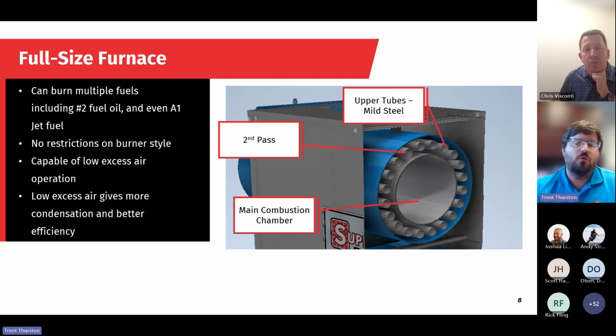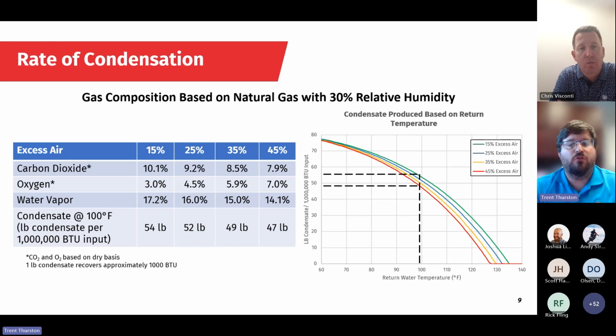Excess air causes a couple issues. One is that you're heating up unnecessary air, and so you're wasting energy by doing that. With condensing boilers, there's another aspect, is that you get better condensation with lower excess air levels. So as we see, when we get higher excess air levels, the water vapor percentage in the flue gas goes down. And so the condensing point starts at the return water temperature and water vapor concentration. At high water vapor concentrations, we'll start condensing earlier, as you see in that graph.